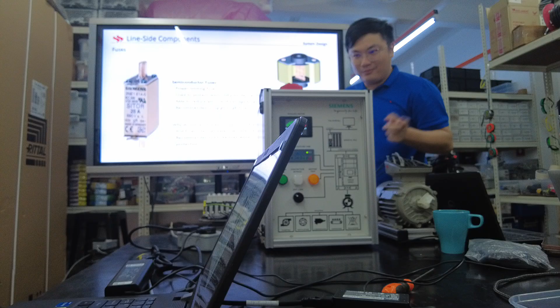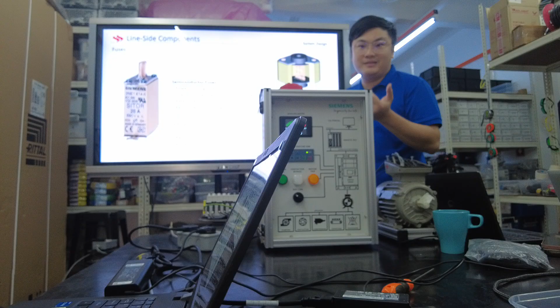We're talking about MCB switching time - simply said, usually this is used for MCCB. Don't talk about the big ones - for the small one, we're talking about 30 milliseconds, 0.03. If it's a big breaker, we're talking about 0.06, 60 milliseconds, or 110 milliseconds, depending on the brand. But based on study, it's about 30 milliseconds. But for fuse, it's 10 milliseconds.